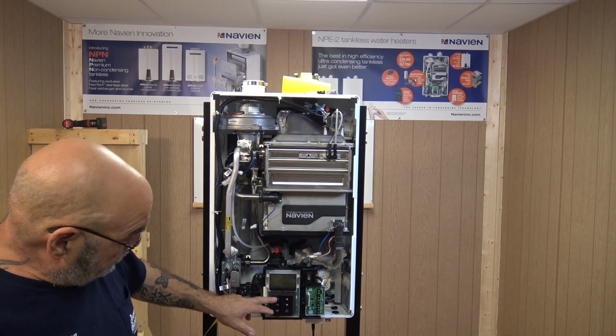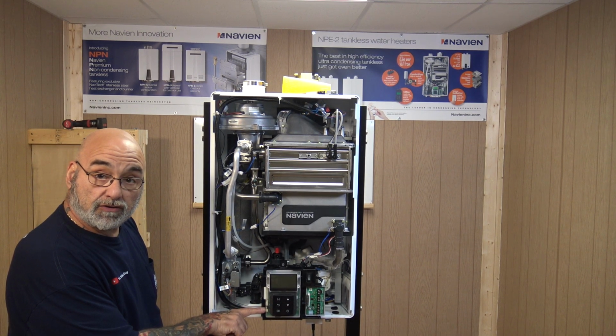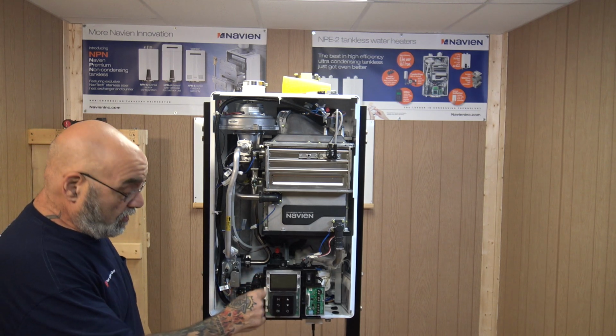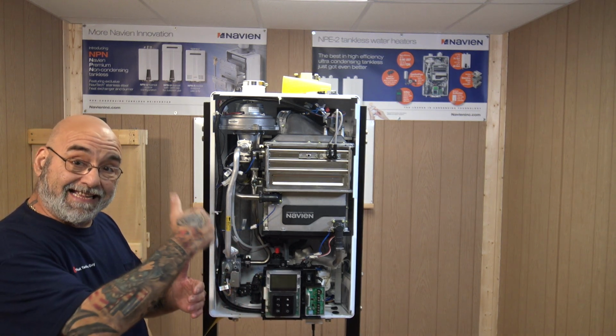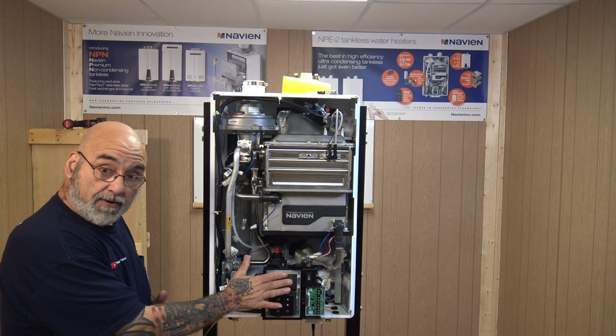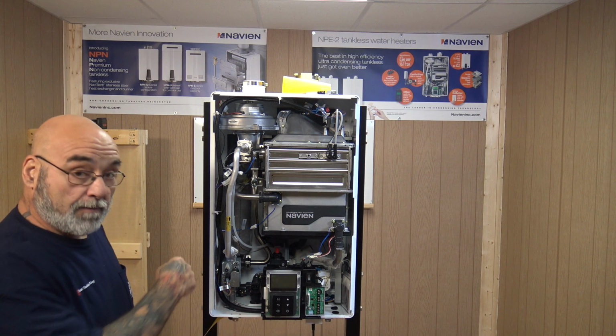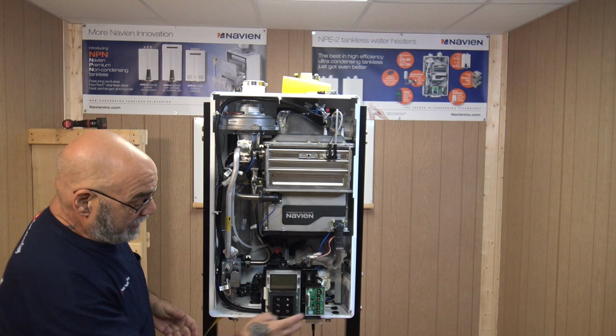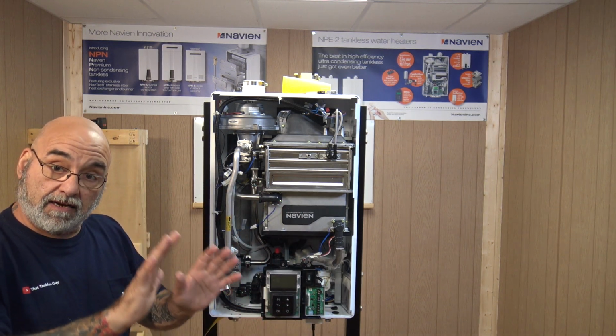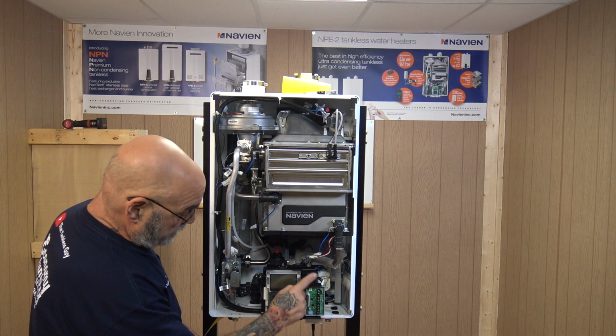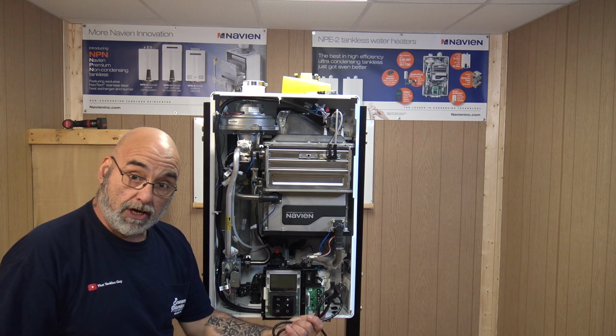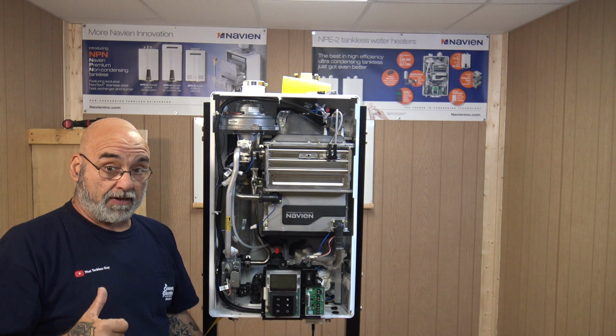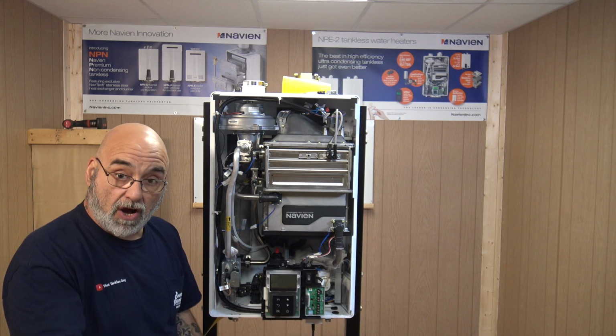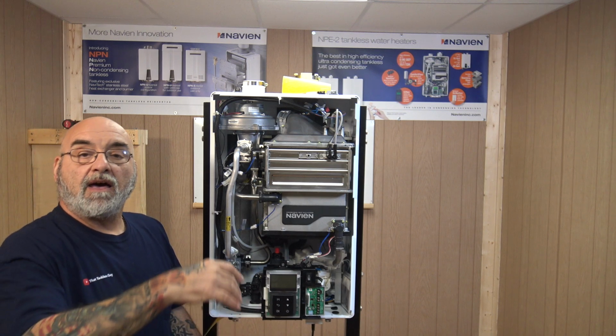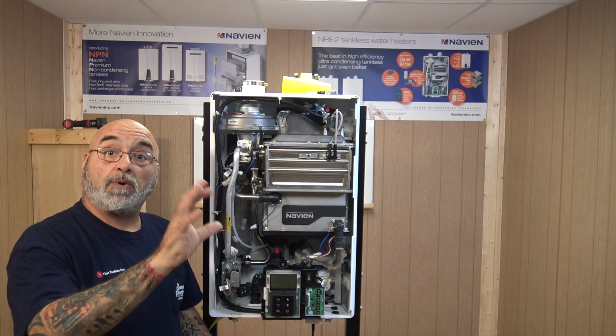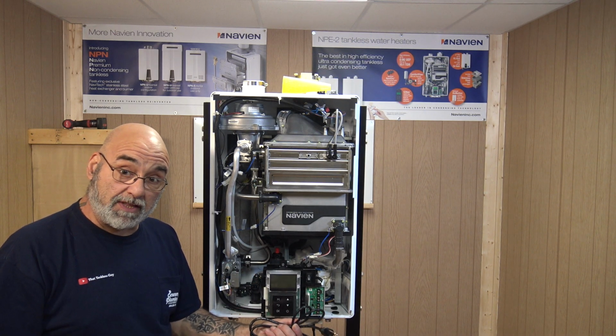All right, so controller. You have the means of an exterior controller. So you can take this controller and run a wire inside the house, and you can put an interior controller so that they don't need to come out here to look at this thing. It has communications cables so you can link these together. It has separate pump terminals. We're going to go all over that in a future video. It has an on-off switch. It has a 5-foot cord, so you do not have to wire it like the NPN model. If it's inside, you need a regular plug, or well, everything's GFI. But outside, you're going to need a GFI with an in-use cover. So just remember, every one of these comes with a cord.